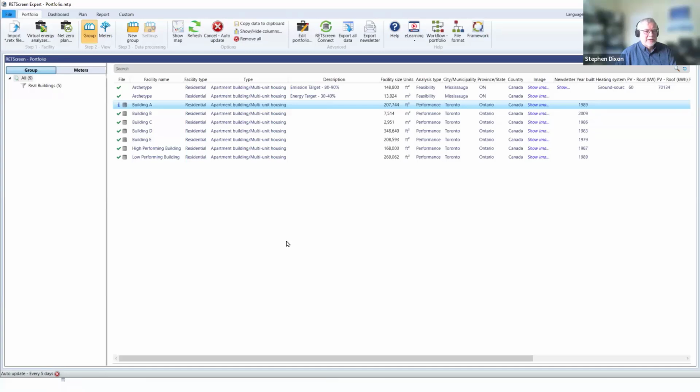So basically, the baseline is a model which compares the actual and the predicted values, right? It develops a linear model, in the case that we were just looking at, and then uses that model to predict beyond the baseline period. So the baseline predicted is what you would have used had nothing changed in the building. The actual is what you actually used. In that chart, you saw the actual versus the predicted. The difference is what we think are the changes in consumption. Could be called savings, could be called an increase, could be called avoided consumption. I hope that answers the question.